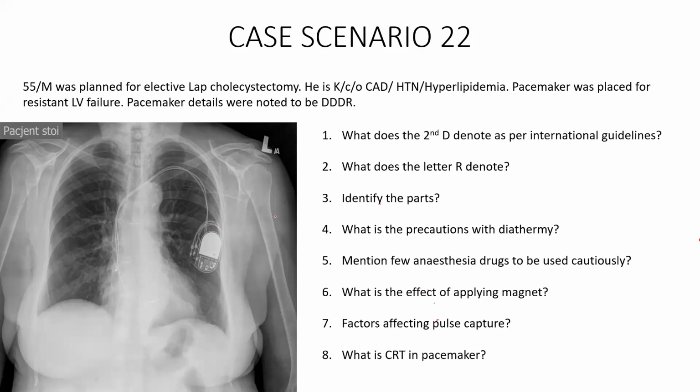Okay, normally, for example, if you fix a rate of 75 per minute, if you fix a pulse voltage output of 75 per minute, this will calculate the time variation of when you have to start working. So the pulse generator will initiate an electrical potential, and it will generate a depolarization at the point where it is stimulating the concerned wall. If it is in the right atrium, it will generate a wave of potential at this point. This depolarization potential is picked up by the surrounding muscle and then the action potential propagates. That's how it starts working.